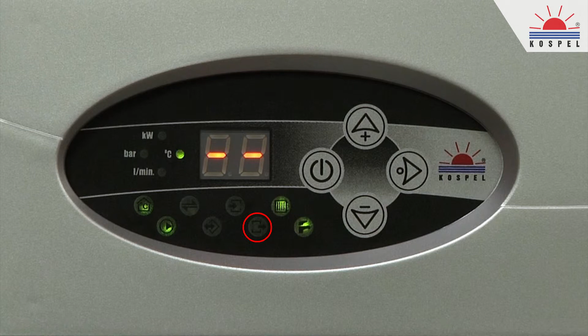In case the bar pressure indicator is flashing, the heating system pressure dropped below 0.6 bars. The boiler has stopped heating and the pump has stopped. Locate the cause of the failure or locate the leak in the heating system. Fix the leak and fill the system with liquid up to the required pressure. If the boiler is still not working, the pressure sensor is damaged. Please contact an authorized Kospel service.